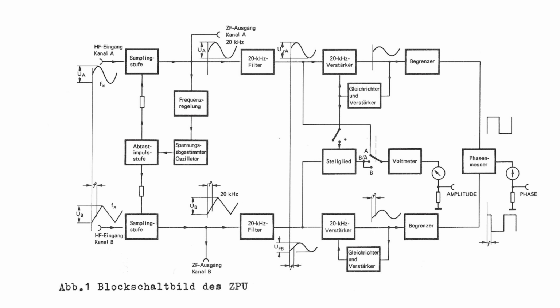Now here you see the block schematics of the device. I don't want to go into many details here, but basically we're seeing back here that we have two completely independent, identical channels that are measuring. Actually, there's one significant difference between the channels still. The first channel cannot accept as small voltages as the second channel. This is a design choice in the device because the first channel also has to be used for synchronization with the auto-tuner here. And that is the reason, according to the manual, it has a different measurement range.